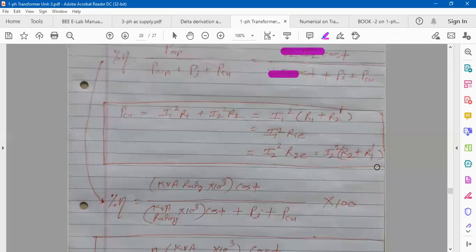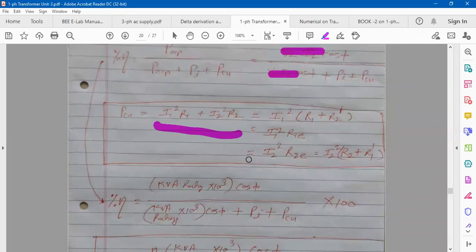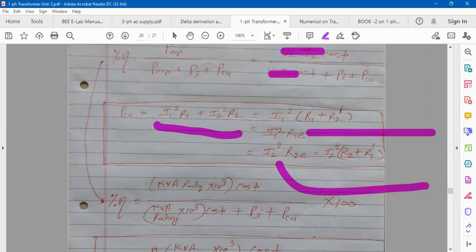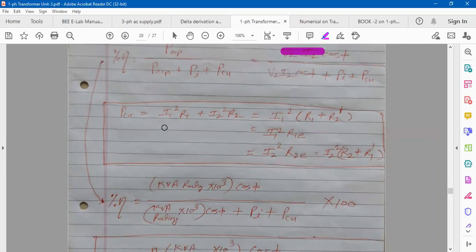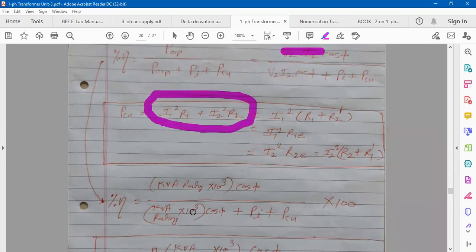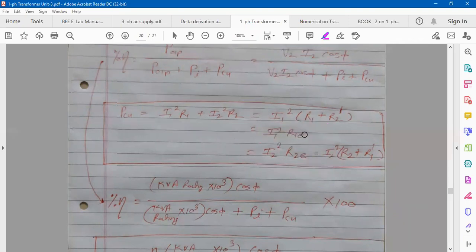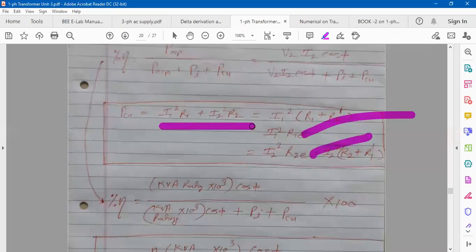Copper loss, as we have seen in transformer parameters, is I1²R1 + I2²R2. When we learned transformer parameters, we also saw the formula for copper loss referred to primary: I1²·R1E, and referred to secondary: I2²·R2E. Out of these three formulas, any one can be used to calculate total copper loss — you will get the same answer.